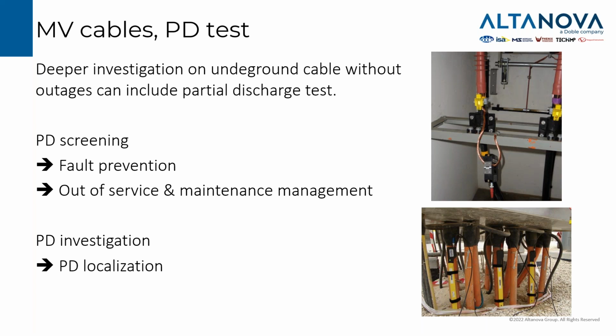So it's quite specific. It's not limited to the termination, so we can also have an overview of the whole insulation system of the circuit. And we can use this test to be performed online without going out of service to prevent some faults or to decide which of our lines need a more accurate investigation by placing them out of service and performing some offline testing. And in some cases, we can also use them to localize defects exactly by means of a time domain reflectometry study of the PD pulse that we have.